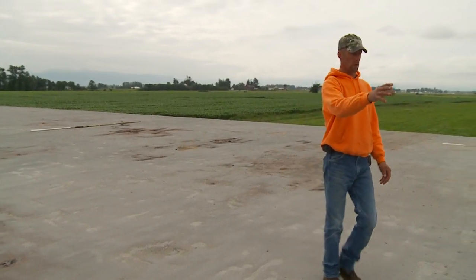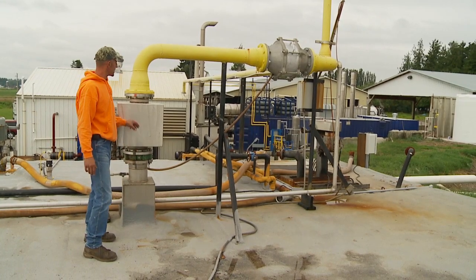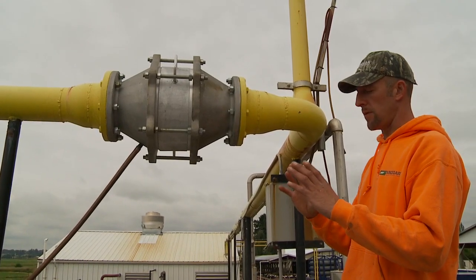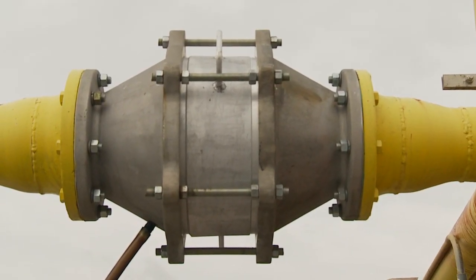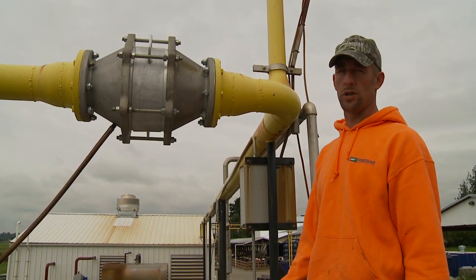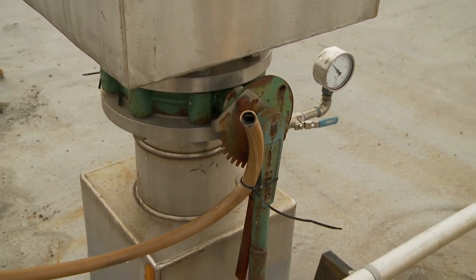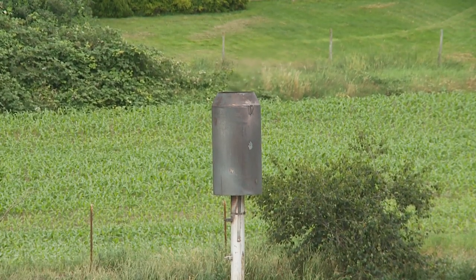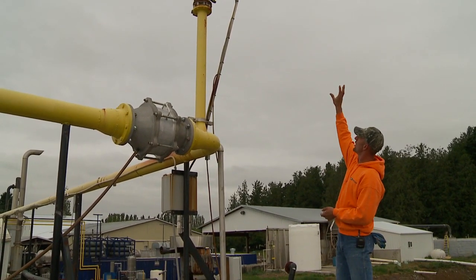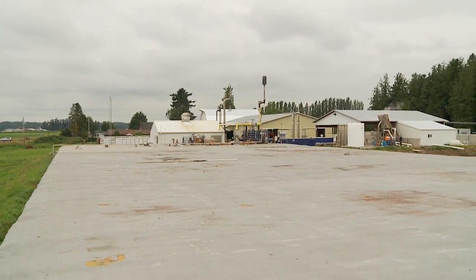After it makes its U-shape, this is where the manure comes out to this area. This is our gas collection box where all the gas from the digester comes through into the pipeline. From here, we have a flame arrestor — it looks like a honeycomb inside and basically prevents it from burning back through it. We'll pull it out every 600 hours or every oil change of the engine, or on a biweekly schedule, and clean it with hot water or a pressure washer. We try and drain the moisture out of the pipeline here before it heads to the cooling. Up above here is the flare relief, where it goes through a one-way valve with weights on it. Once it gets to a certain pressure, it will relieve the excess gas and burn it with a sparker — we'll flare it if it's not needed or if we have more than we can use.